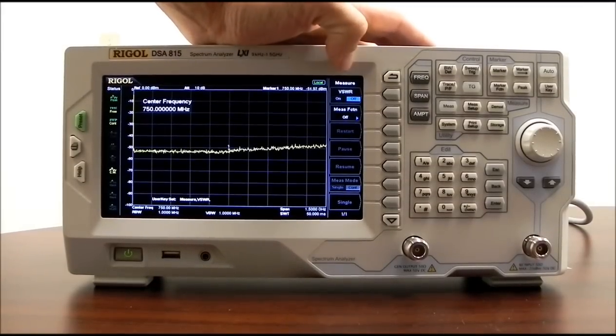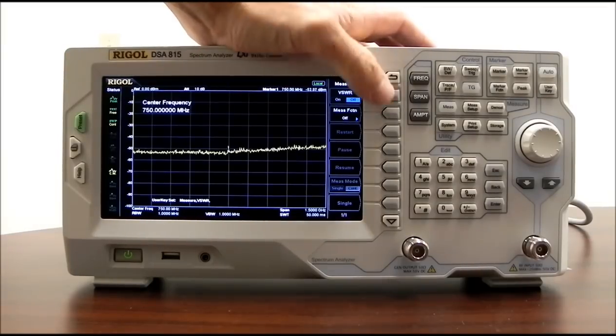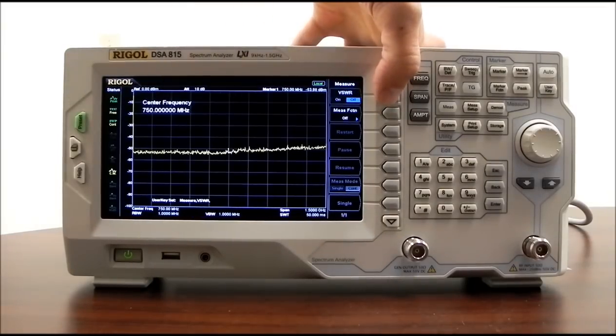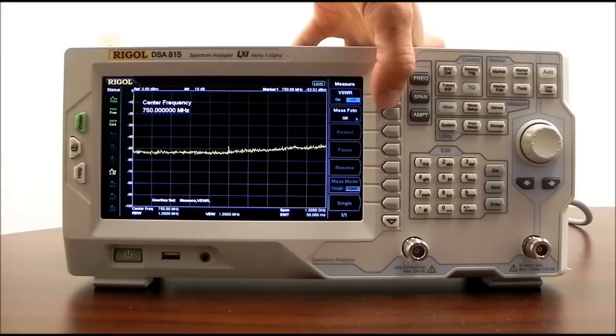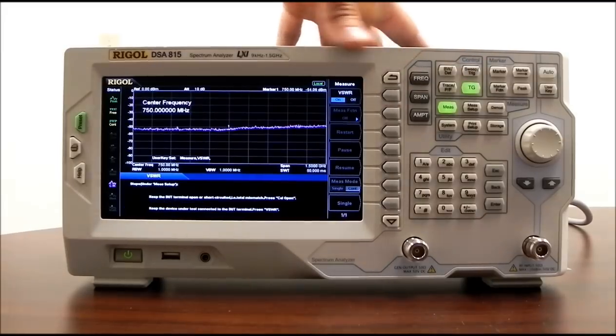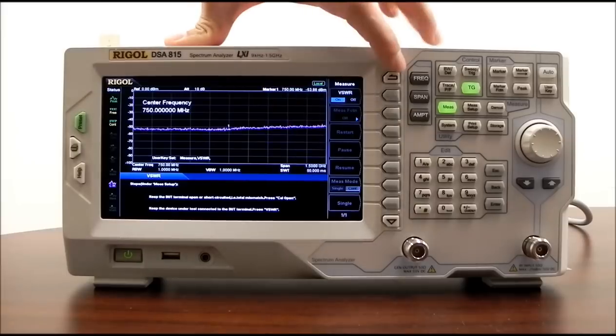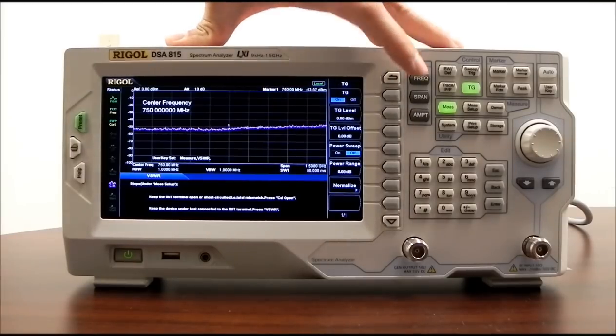We have an additional option for VSWR measurements. That's a software and hardware option. In the VSWR measurements, if you're going to be measuring VSWR for antenna, this makes the math quite a bit easier and displays the VSWR on the front panel here for that particular antenna.